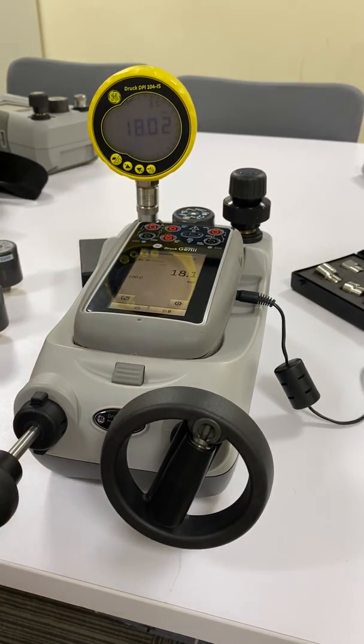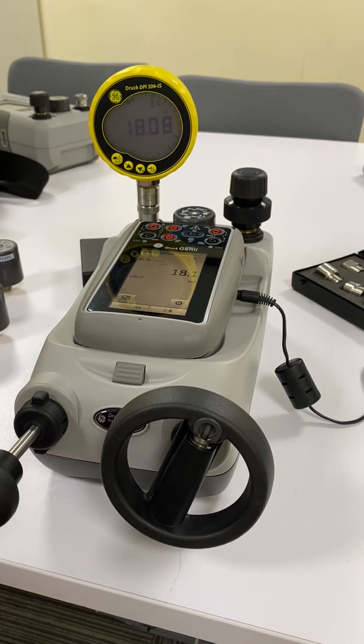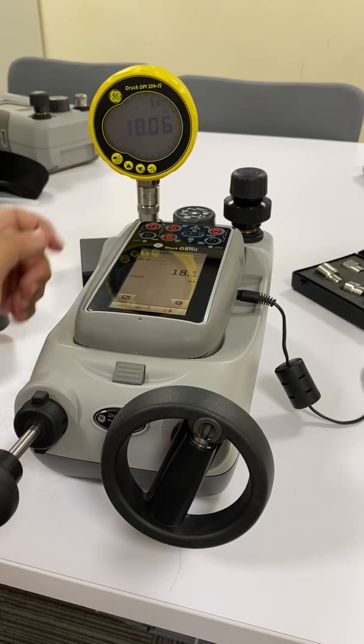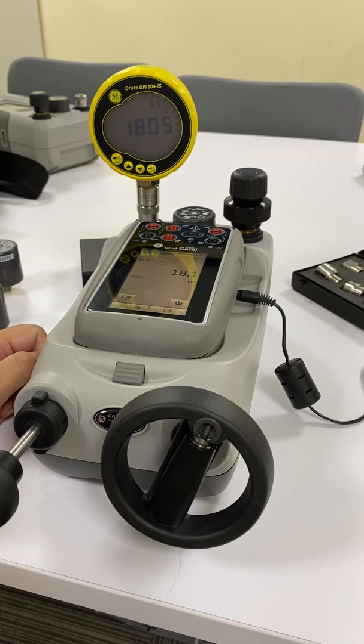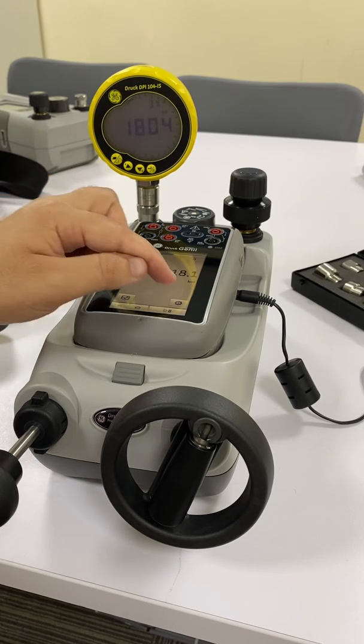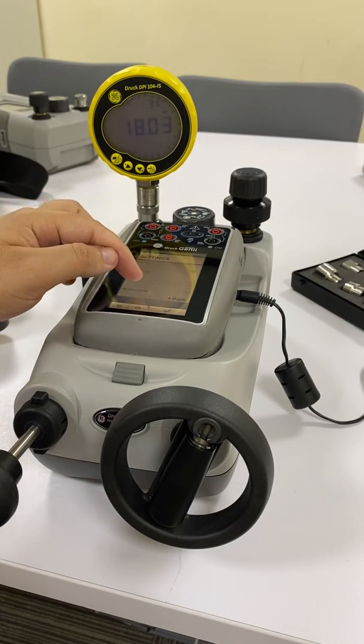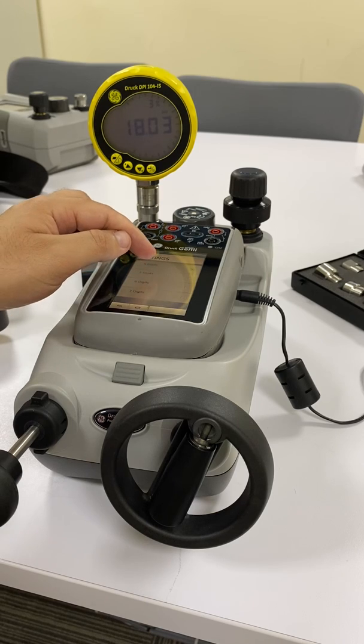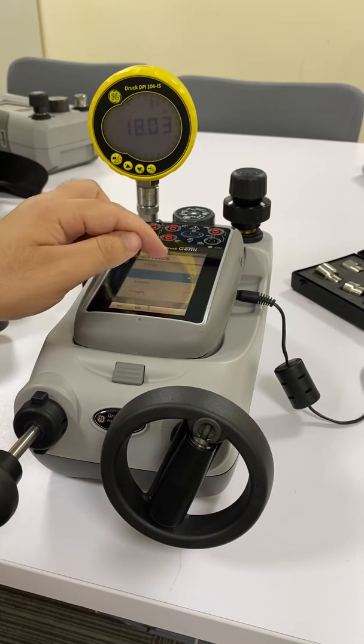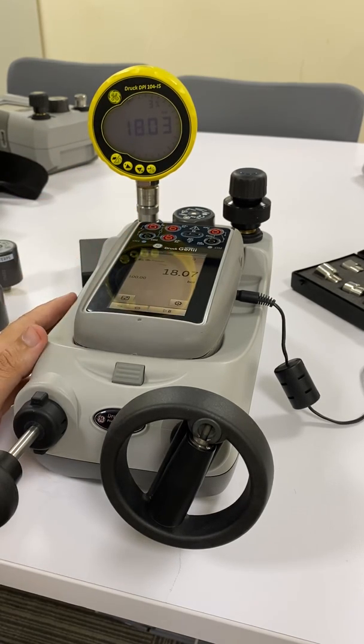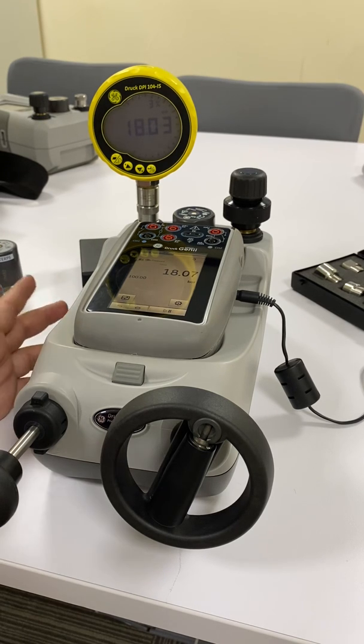Let's take a break now and see. 18.1, 18.05. We are not sure, we need to match the digits to be sure that we are doing it right. So I'll increase it by one digit now, increasing the resolution. So I have a difference of like 0.04 bar. Comparing that to the full scale, this is nothing, but this is an error at the end which we need to document.